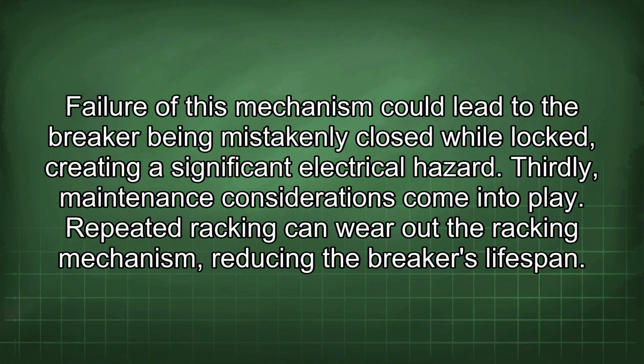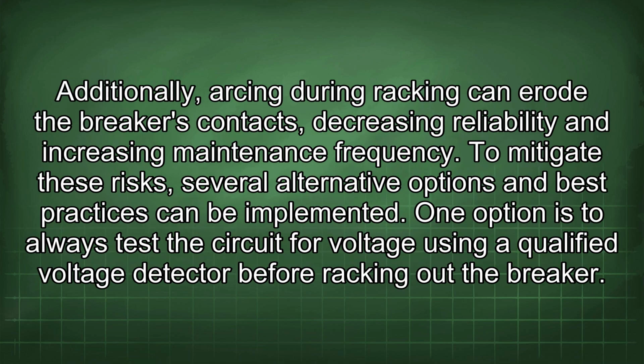Thirdly, maintenance considerations come into play. Repeated racking can wear out the racking mechanism, reducing the breaker's lifespan. Additionally, arcing during racking can erode the breaker's contacts, decreasing reliability and increasing maintenance frequency.